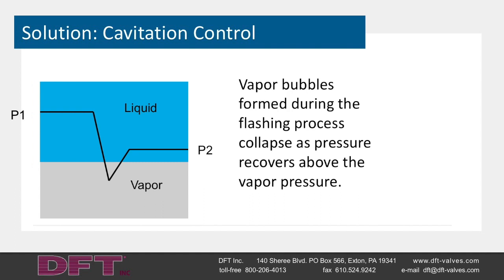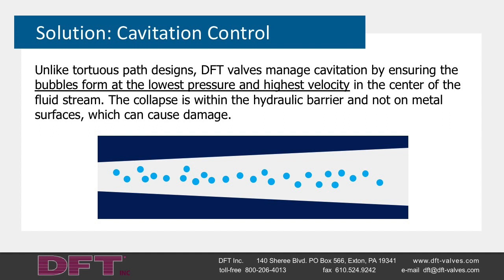Solution: cavitation control. At P1, the fluid stream is all-liquid. Liquid flashes at the valve port when the pressure at the vena contracta drops below the liquid vapor pressure. As the velocity decreases in the exit nozzle, the pressure increases or recovers to P2 and the vapor bubbles collapse — this is the point at which the potentially damaging cavitation occurs. Unlike tortuous path valves, straight-through Venturi control valves manage cavitation: bubbles form at the lowest pressure and highest velocity in the center of the fluid stream, and the subsequent collapse is within the hydraulic barrier, not on the metal surface. The diverging nozzle provides smooth recovery prior to the fluid exiting the valve.